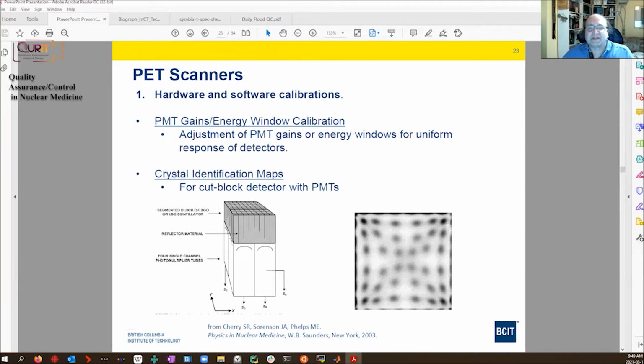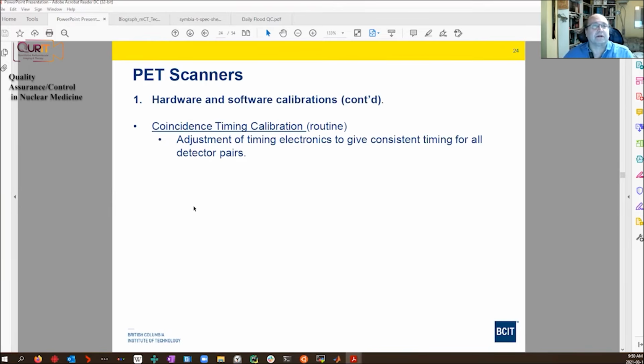So what you want to do is you have to set up areas where you say anywhere within this area in the identification map corresponds to a gamma ray hitting this crystal. So this is a calibration that is done for these type of block detectors. More modern block detectors have one of these elements coupled directly to an avalanche photodiode or a silicon photomultiplier. And so you don't have to do this addressing based on light distribution. And so it's easier. Again, Armand would be able to describe this in more detail.